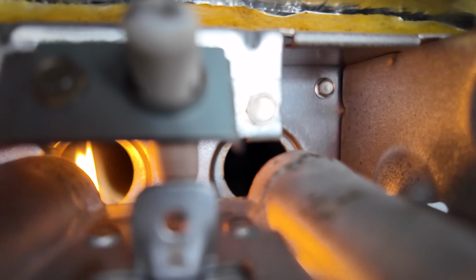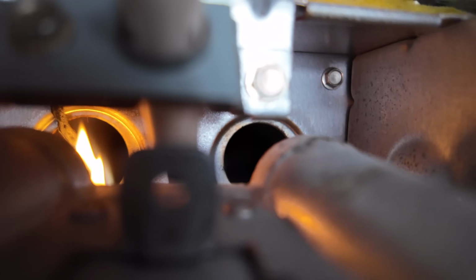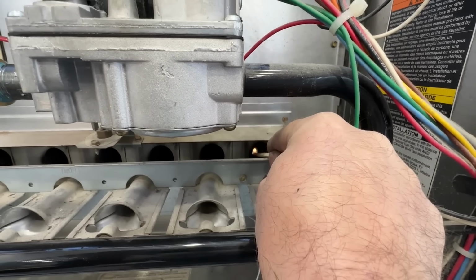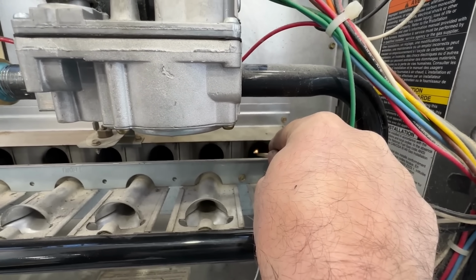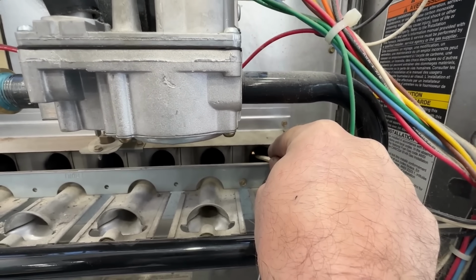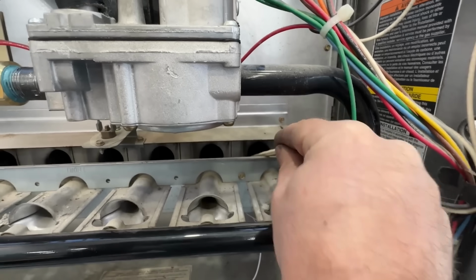If the flame dances around a lot or gets blown out in one of the tubes, you know there's a crack or a leak there. When there's a hole in the heat exchanger, the air from the blower fan will leak into the heat exchanger tubes and put out the flame or make it visibly dance around.